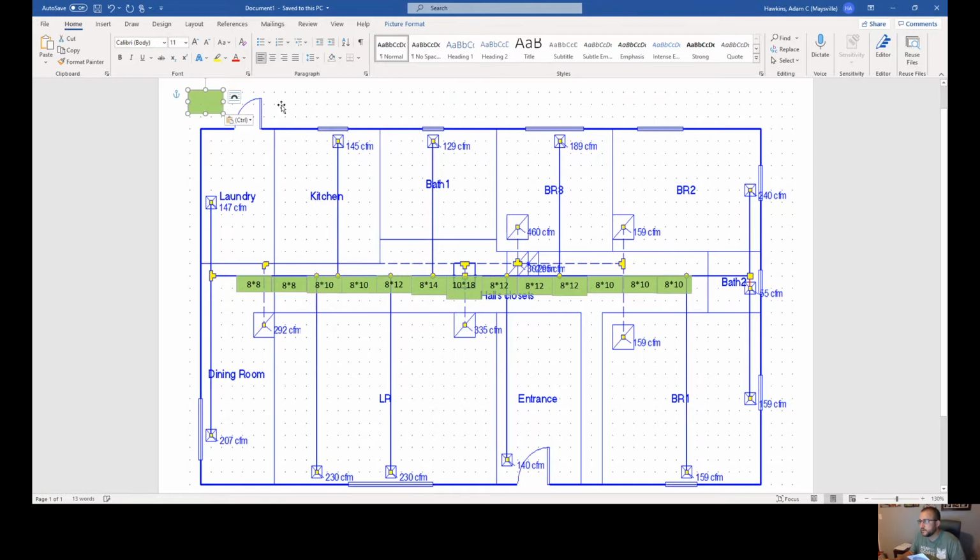I had 100 come out of that one. So now you're going 350 minus 100, so 250 at 0.1. That puts you at 8 by 7, so we're going to go 8 by 8. Never go smaller than 8 by 8. And that's probably going to be my last piece, because I can get the rest of those from there.